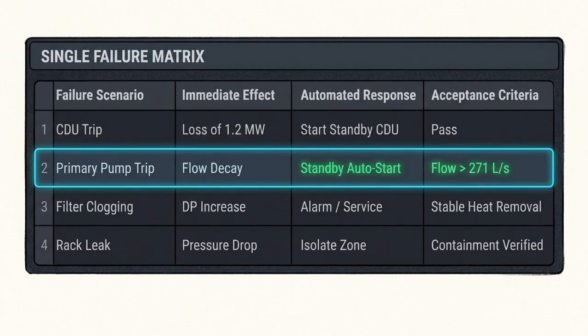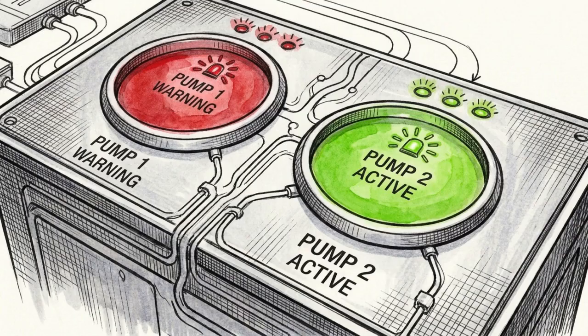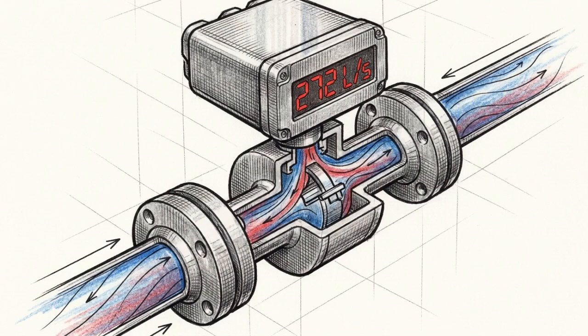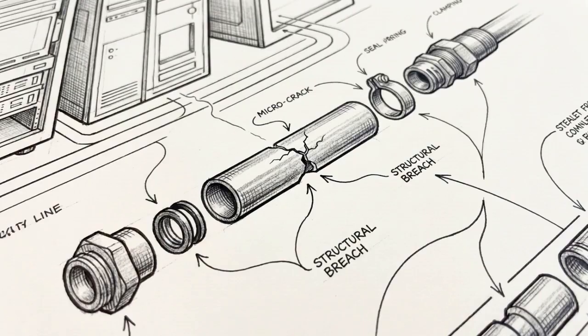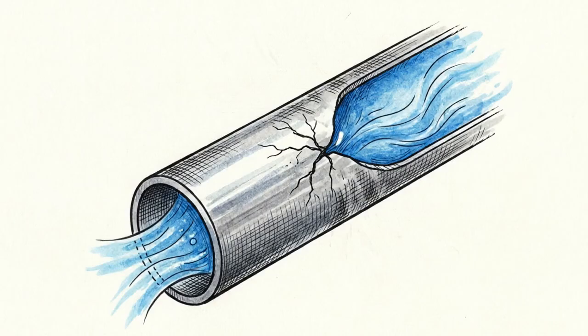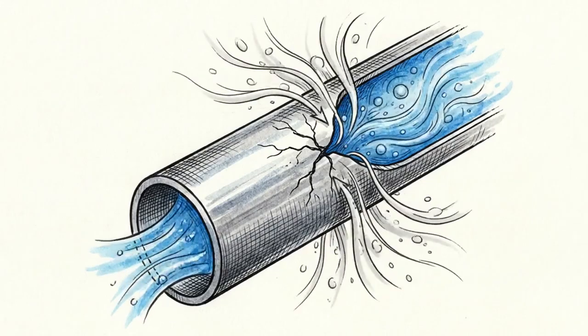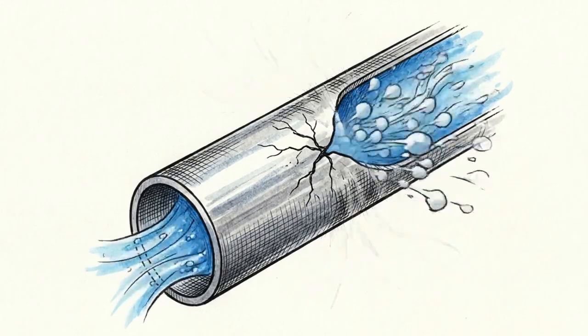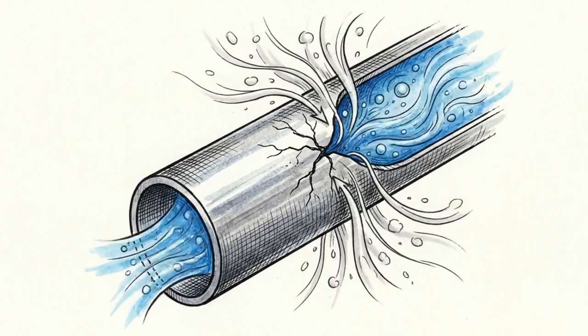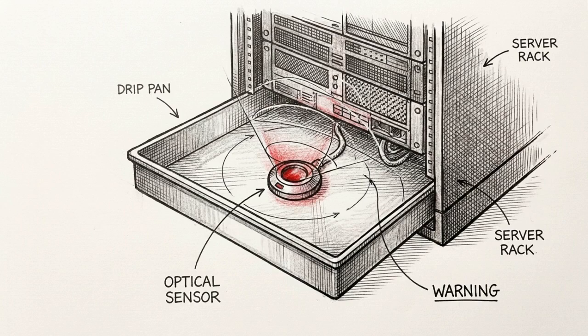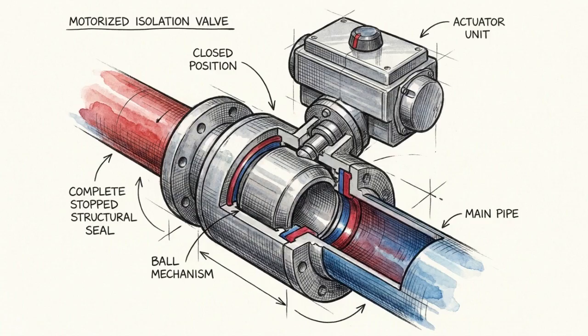Let's examine the deterministic fault matrix. In the event of a primary pump trip, the system detects the flow decay. The standby pump engages instantly to maintain flow above 271 liters per second, preserving full cooling capacity. If a catastrophic chip-side fluid line breaches, the CDU utilizes negative loop pressure management. Instead of spraying liquid out onto the electronics, it pulls a vacuum and draws ambient air inward. Simultaneously, optical drip pan sensors alert the leak sentry matrix. Motorized isolation valves shut down the local loop feed in under 10 seconds, preventing a multi-rack fluid loss.